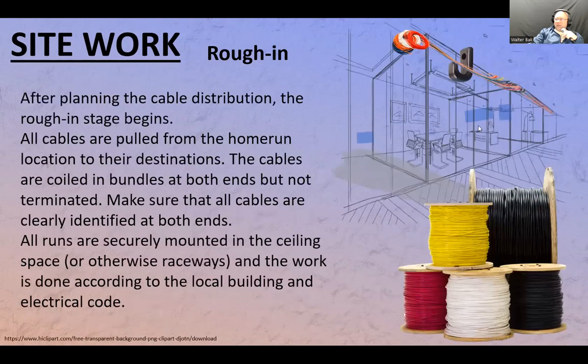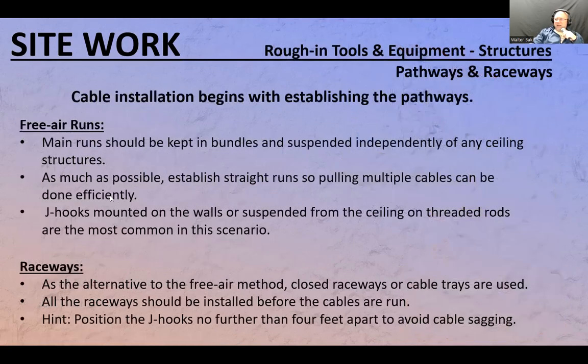All right, I'm going to go back to this same picture here. If you have to do a straight line from here to here, and you have 12 or 15 wires, yes, one person is going to feed that there, and the other person is going to pull from the other side. You can establish a good flow when pulling the wire. If you have to do a bend around the corner, then there are some tricks you can apply to do maybe one bend around the corner. But if you're starting out, just make sure that you do straight lines. So that's basically what that thing here means.